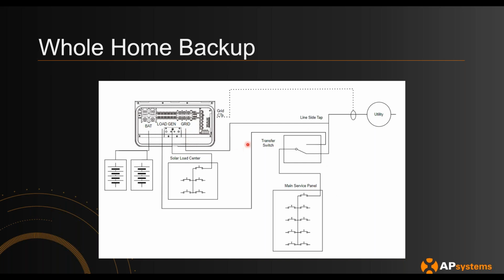Now the PCS is line side tapped into the utility. In this configuration, you'll be able to use the batteries to push power onto the loads if you're in self-consumption mode, and it will also be able to charge from the solar as well. So if you have solar connected here, it will take that solar power and charge the system. That's the purpose of this line side tap.